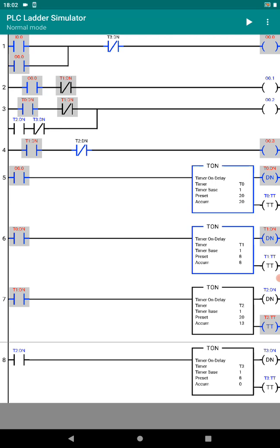The program has three main outputs. If you look at the diagram you will see four outputs, but one of them is just an internal relay to latch and launch the program. The input/output 00.0 is that internal relay. You could also do this program without latching it, but I've latched it so it stays in a continuous cycle.